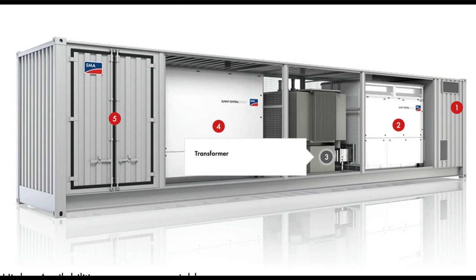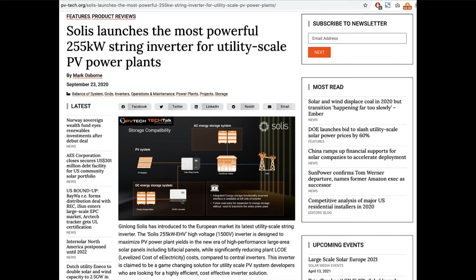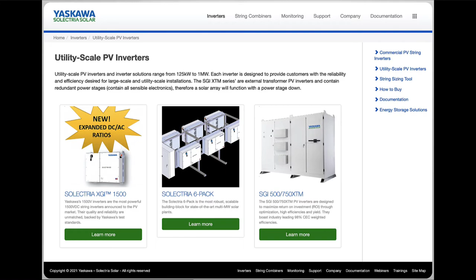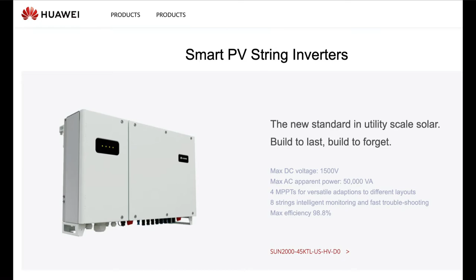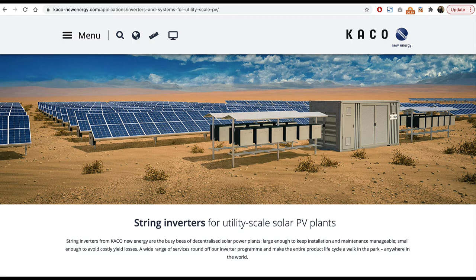Some of those are a single inverter in that range to a transformer. Others, certainly string inverters have become a common method and are becoming more common. That's something I've worked on in my career, coming up with inverter cluster concepts that connect directly to the secondary of a transformer without switchgear or anything like that. That concept, I think, can ultimately get you in a range similar to very large central inverters, but you're dealing with 250 kilowatt inverters that are far easier to maintain and more likely to have multiple options for replacement.